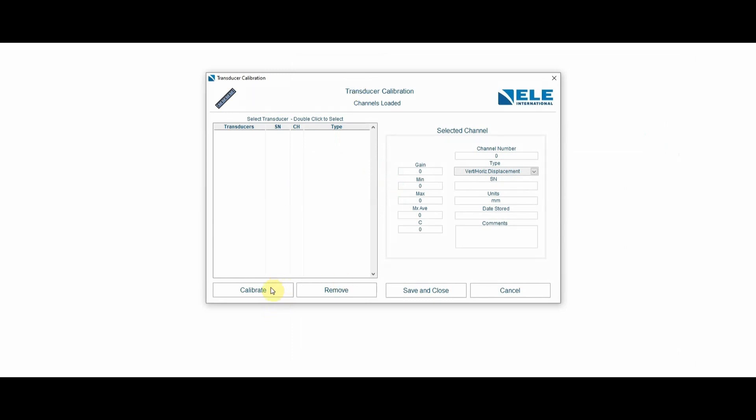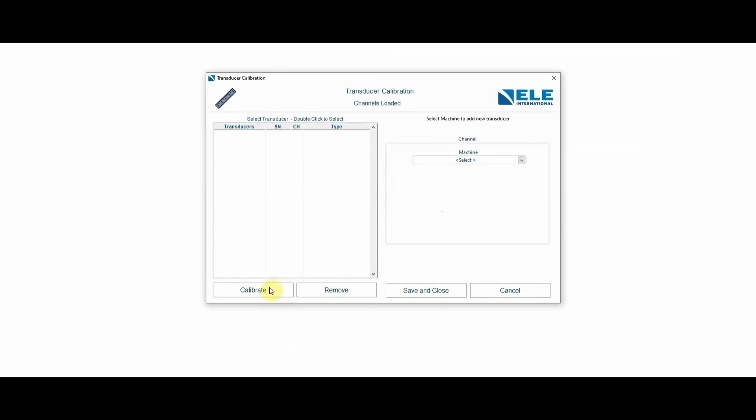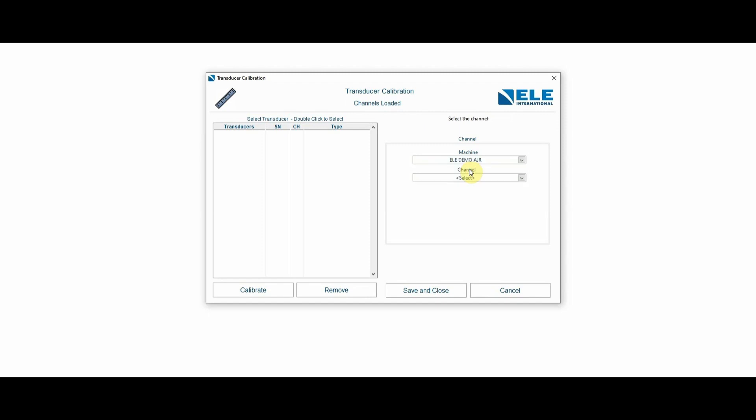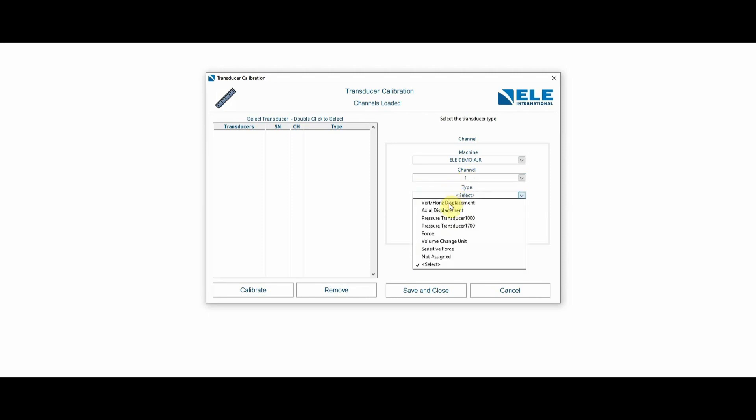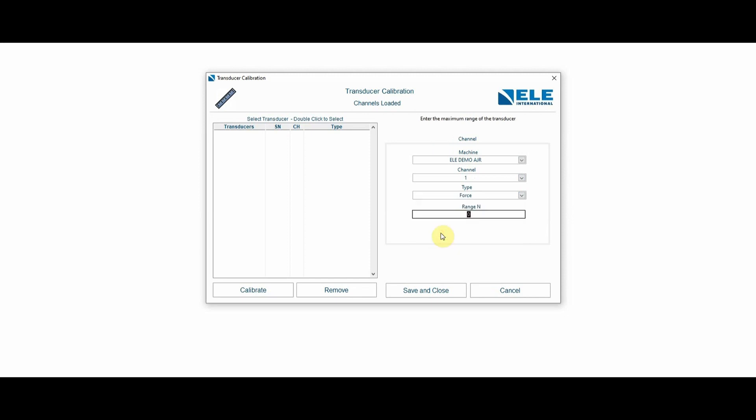We're going to enter or calibrate a new transducer. I'm going to enter the calibration of the transducer and add it to the ELE demo machine that I'm pairing it up with. Select the logger channel. Logger channel is going to be logger channel number one, and the type of transducer is going to be a force transducer. The range of this is going to be 15,000 newtons or 15 kilonewtons.